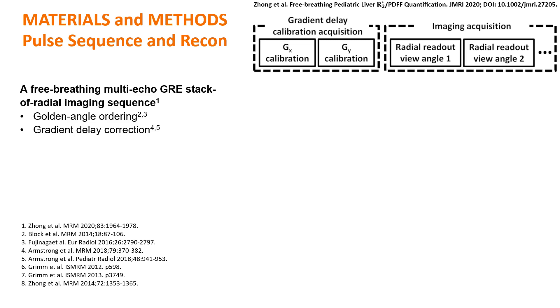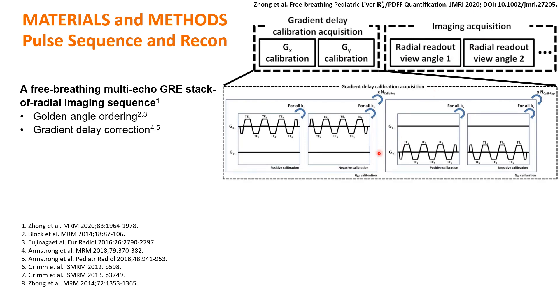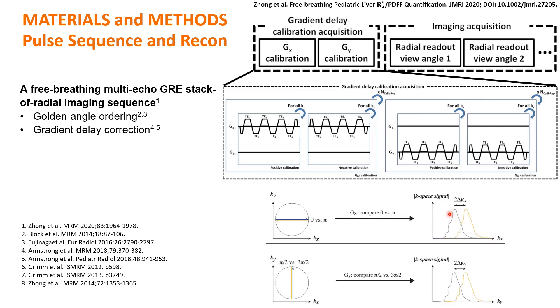This slide summarizes the pulse sequence and the reconstruction of the proposed method. This multi-echo GRE stack-of-radials imaging sequence consists of a gradient calibration acquisition module and an imaging acquisition module. The gradient calibration module acquires calibration lines crossing the K-space origin in the K-X and K-Y directions, then performs cross-correlations to calculate the gradient delay shift terms and uses them to correct the imaging K-space data.